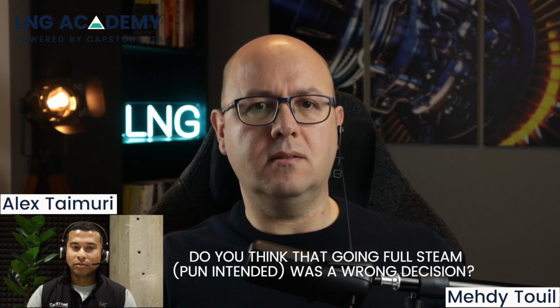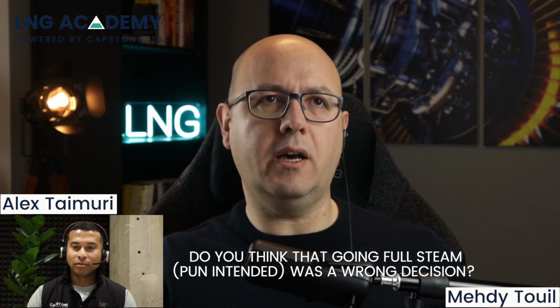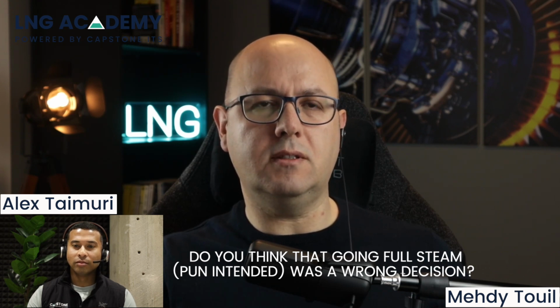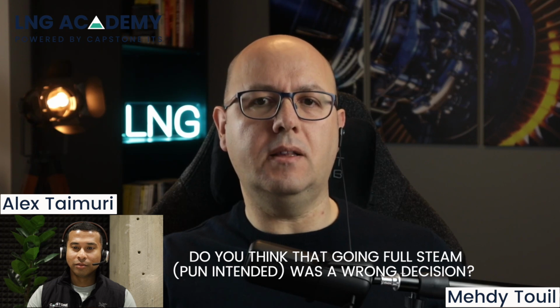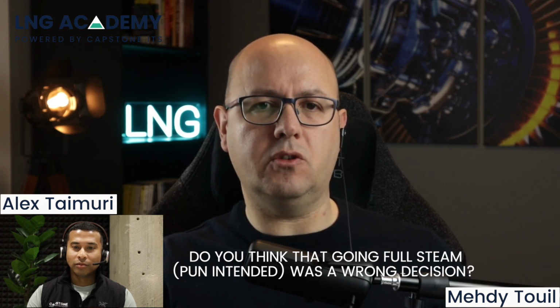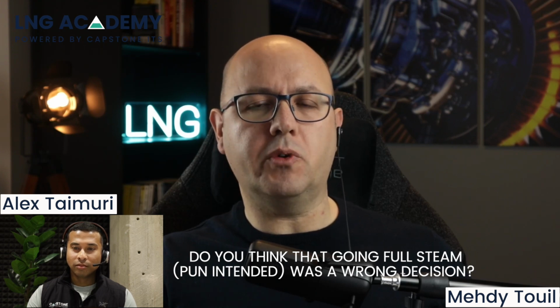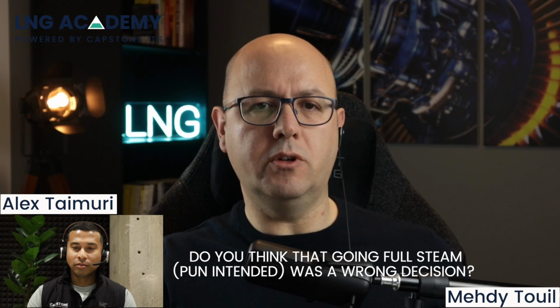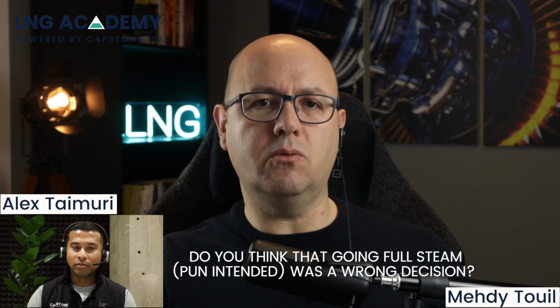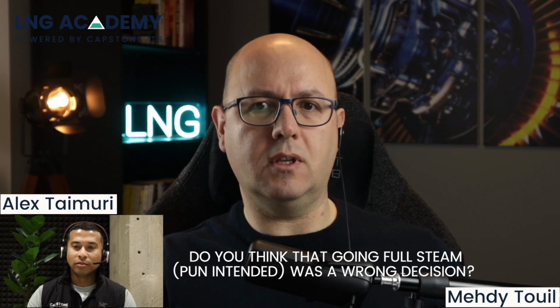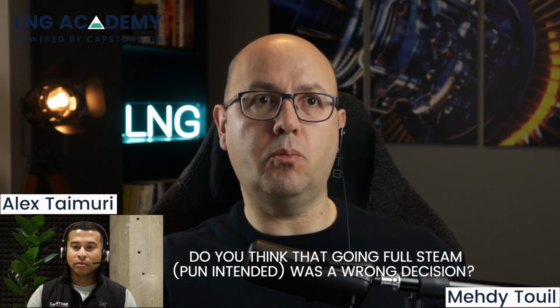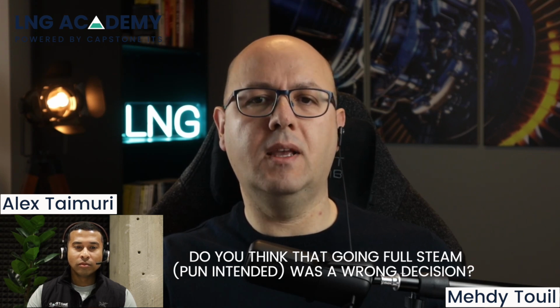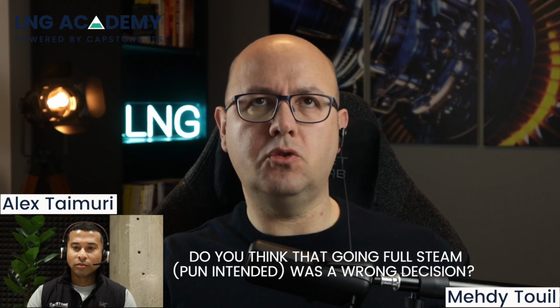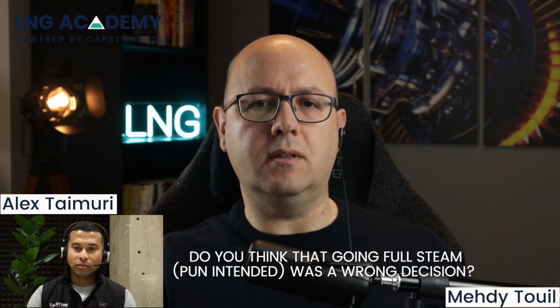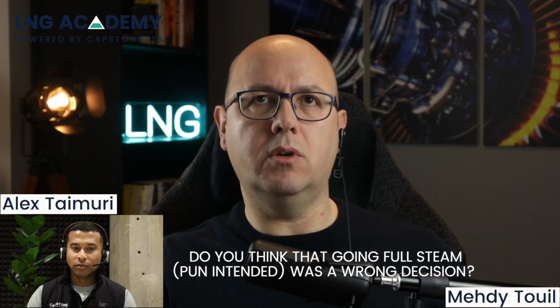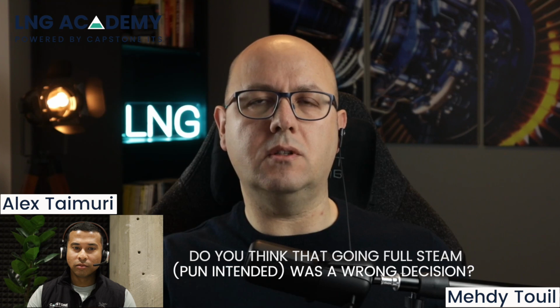As for steam turbines, in contrast to the gas turbines, steam turbines have higher reliability in terms of maintenance. They can run over a wider range of speed, and they are not impacted by changes in ambient temperature like the gas turbines. So you also eliminate the high pressure piping needed for the fuel gas systems, a bonus for offshore facilities. So no, I would say that Prelude troubles are not the result of the steam turbine configuration per se, for both the compression and the power generation. It is true that there were some integration issues between the steam turbines, the generators, and other systems on the facility. But I've heard that those issues were sorted out in 2020.